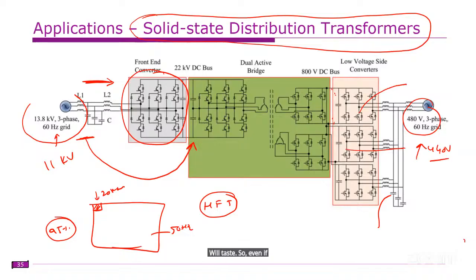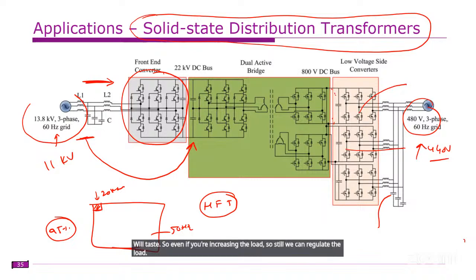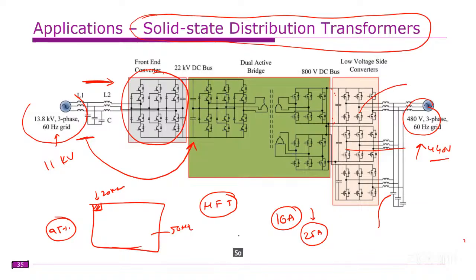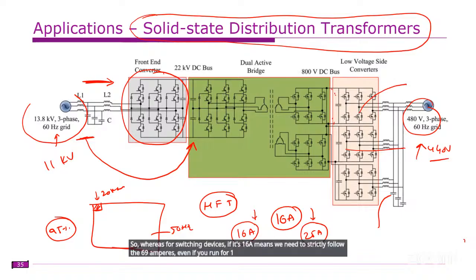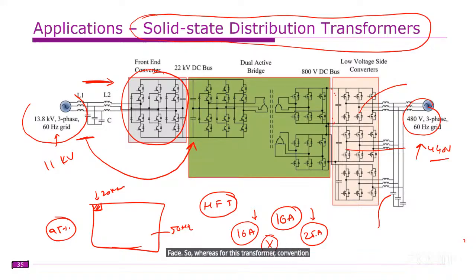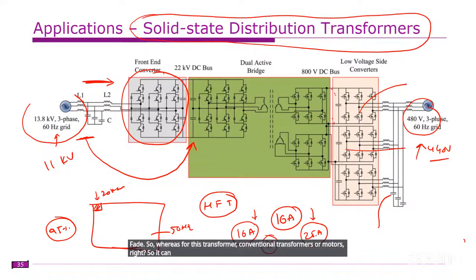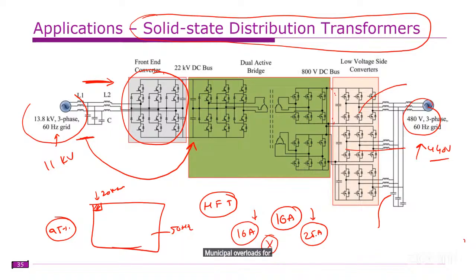Even if you're increasing the load, we can still regulate it. But there are some drawbacks as well. These devices are not as rugged as conventional transformers because switching devices are used, and they normally will not withstand overloads. For example, if you design a motor rated for 16 amperes, you can usually go up to 25 amperes for a short duration. Whereas for switching devices, if it's rated 16 amperes, you need to strictly follow that rating. Even if you run it for 1 or 2 minutes beyond that, the device will completely fail. Conventional transformers or motors can withstand overloads for longer durations.